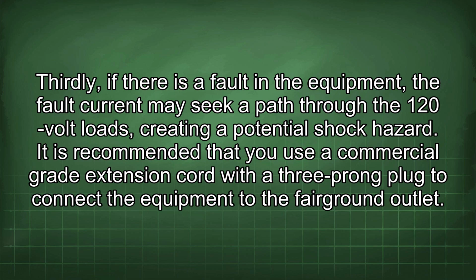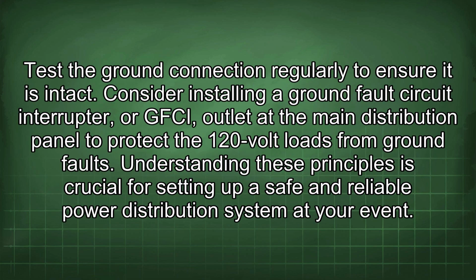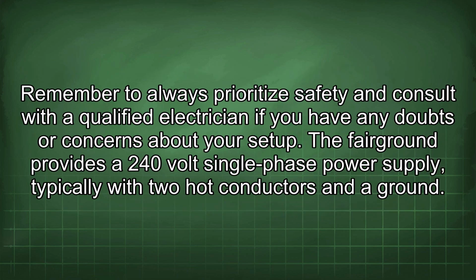It is recommended that you use a commercial-grade extension cord with a 3-prong plug to connect the equipment to the Fairground outlet. Test the ground connection regularly to ensure it is intact. Consider installing a ground fault circuit interrupter, or GFCI, outlet at the main distribution panel to protect the 120-volt loads from ground faults. Understanding these principles is crucial for setting up a safe and reliable power distribution system at your event.